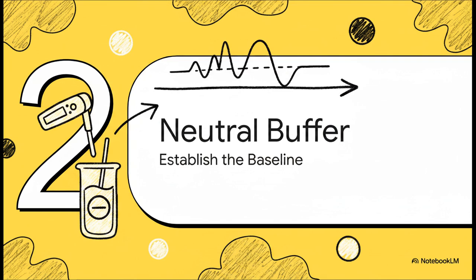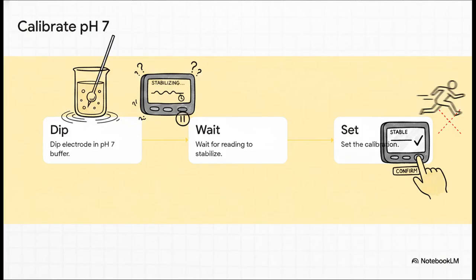Section 2. Calibrating with neutral buffer. Establishing the baseline. So you're going to dip the electrode directly into the neutral pH 7 buffer. Now, why do we always start here? Well, because 7.0 establishes the instrument's electrical 0 point. It aligns the meter perfectly before we stretch it out to those extreme ends. The absolute key here is patience. You must wait for that reading to completely stabilize before confirming and setting the calibration. If you rush this step, every single measurement you take afterwards is going to be inherently flawed.